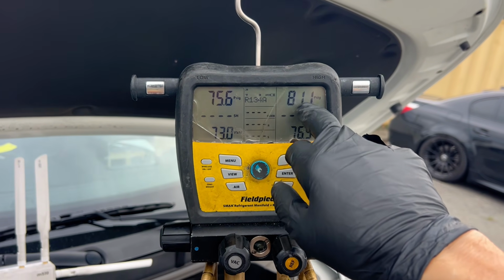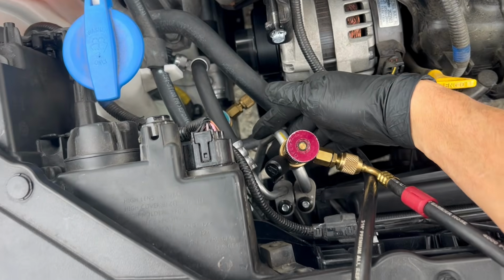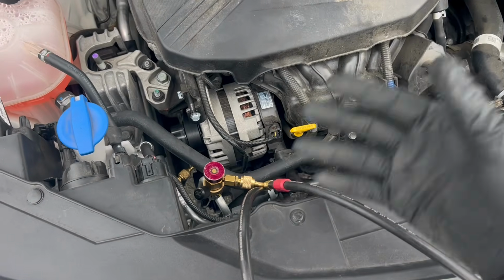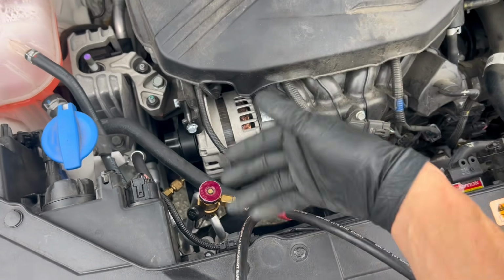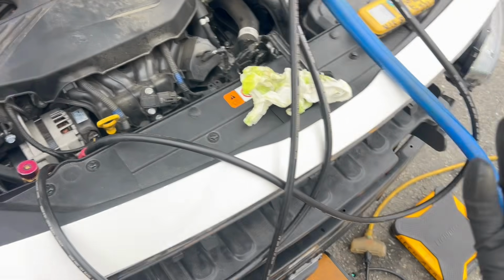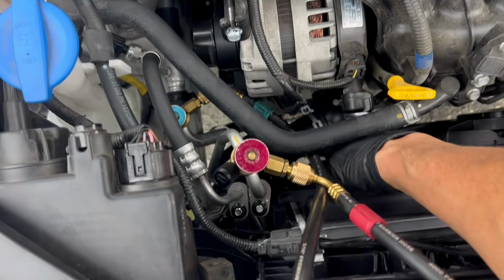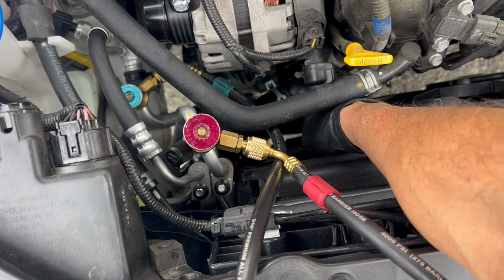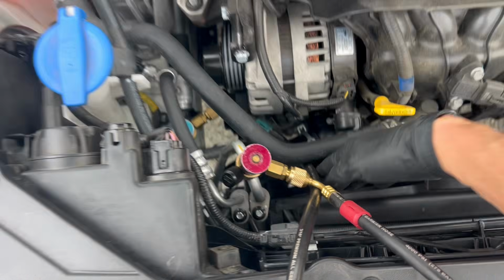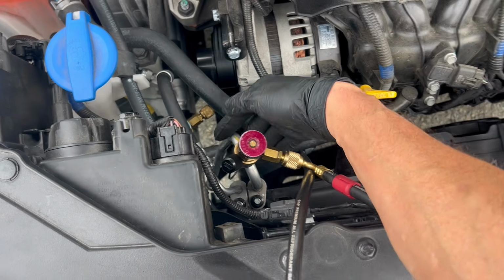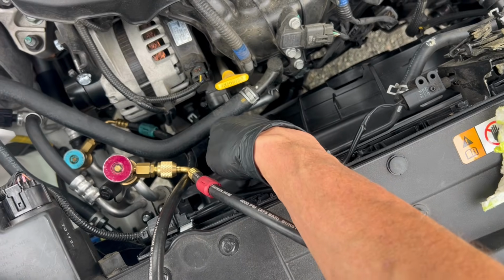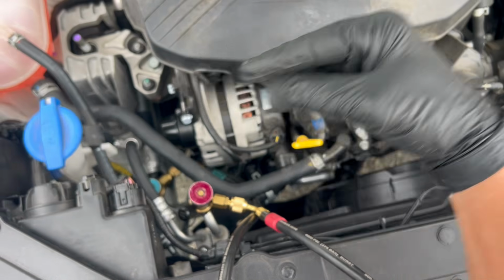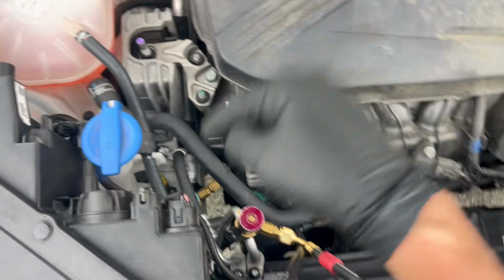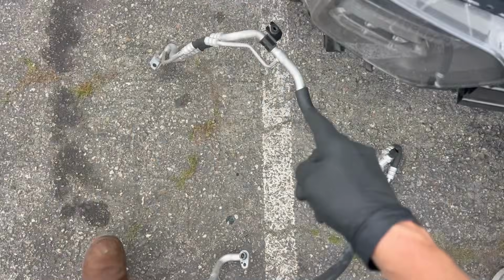So say it says 130 PSI, or 118, depending on the PT chart and the compressor and everything like that, it might be close, and you go, well, that's good, there's no problem there. But if you have the temperature and you're 179 degrees going into that hose, and you're 120 degrees coming out of the hose, that means you have a partial restriction from the collapse of the inner lining of the hose. And you can do that at every section of this hose.